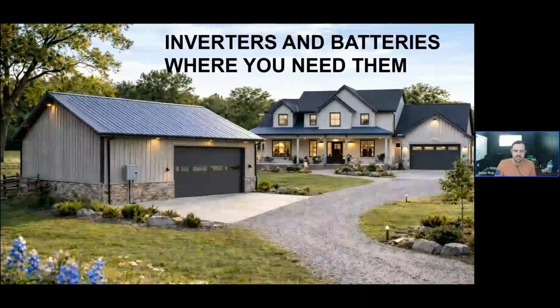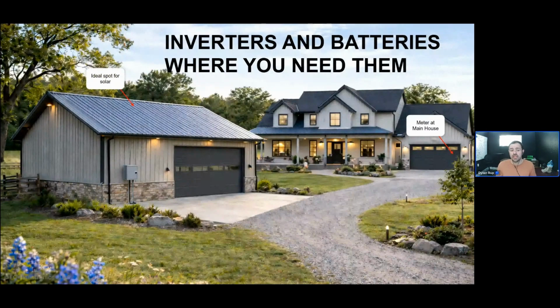Now, looking at the locational flexibility, we talked about it in the context of rugged outdoor exterior, but even beyond that, what this system enables you to do, like I said on the previous slide, is deploy the different components of the system where it makes sense to minimize the amount of site rework that needs to happen. So if we look at an example site here, maybe we have a home with an external garage or shed. The main meter for the home is located at the main house, but maybe the ideal spot for the solar is actually on that shed. Potentially that's the only southern facing roof line of the property that's going to deliver a significant amount of energy production for the site. And then we can further imagine there might be a sub panel and an existing run already over to that shop from the main house distribution panel to get power over to that shop.